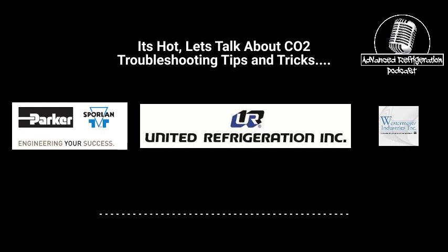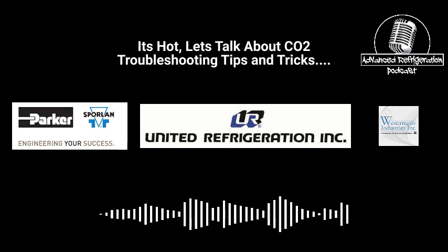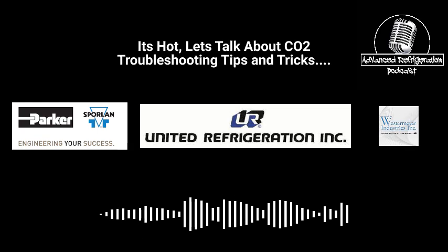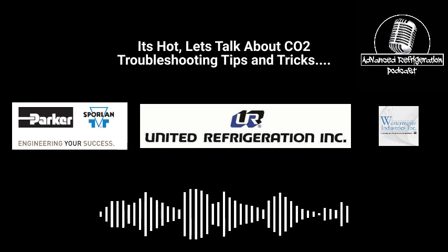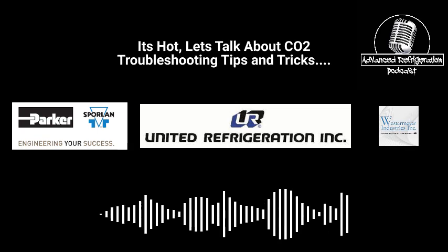Now, what I've found at most of these sites is they usually have a 5-second pulse on and a 20-second pulse off. It's not enough. So I usually go anywhere from 10 to 15 seconds pulse on and then a 20-second pulse off. Let it pulse on longer and drain the oil out of there.